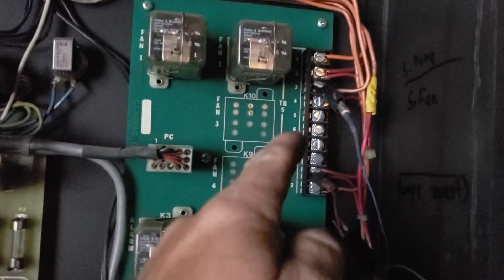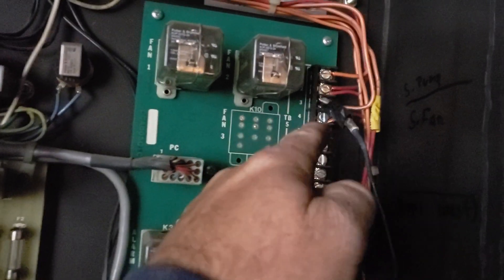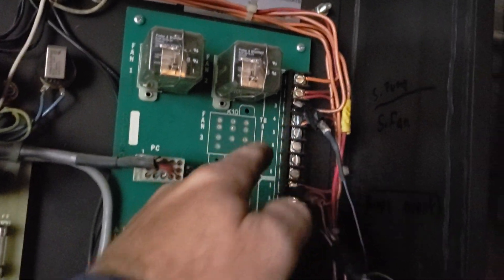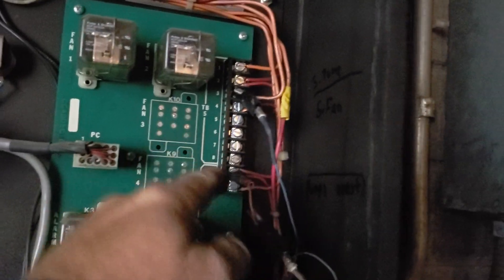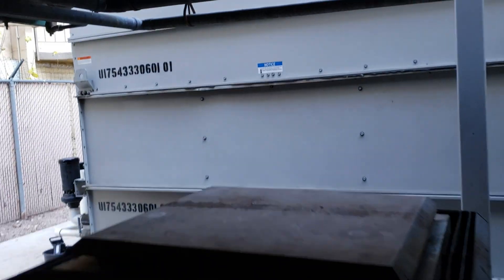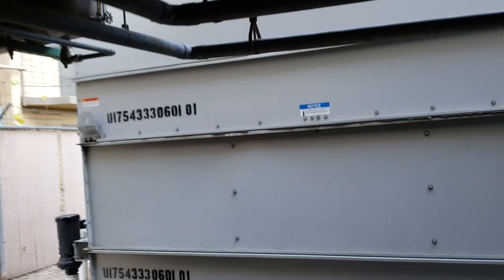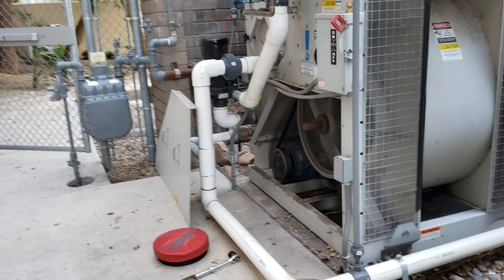Using my alligator clips across 120 hot and then to each relay's dry contact output, flip my switch, sends the 120 volts over to the motor starter, and then my towers start.